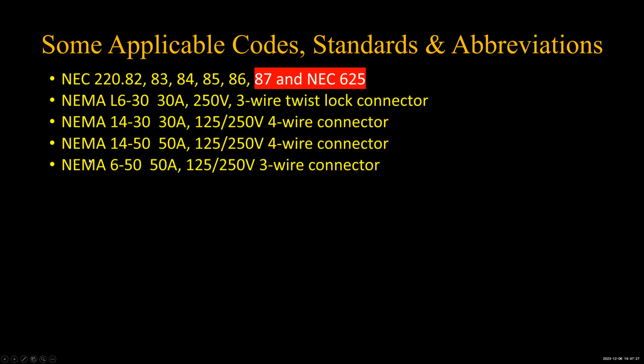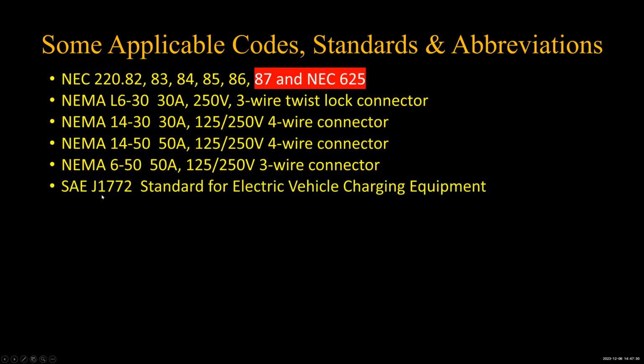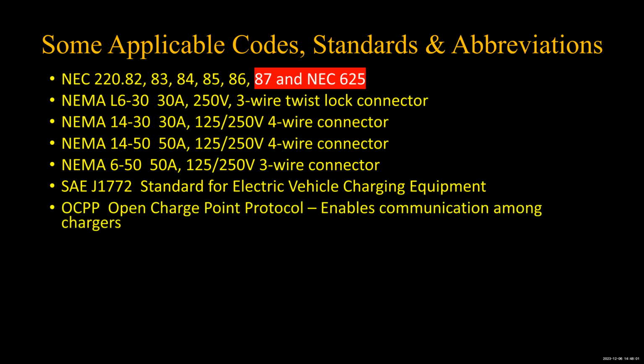And then these are NEMA standards for connectors, and then we got the SAE J1772 for the thing you plug into the car itself. And these are all pretty well standardized, thank goodness. Otherwise, there'd be that nightmare that occurred before we standardized nuts and bolts into a certain number of threads per inch and diameters and stuff. Well, now you get a 1224 or an 832 any place you want to, and they're standardized. And of course, the communication ought to be standardized as well. And that's the Open Charge Point Protocol. And that is how a lot of the chargers talk to each other.